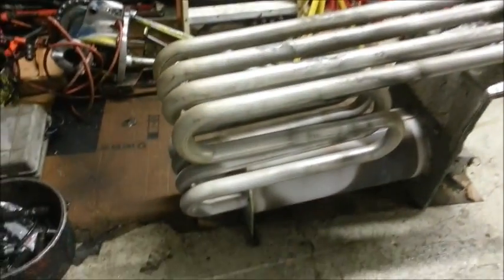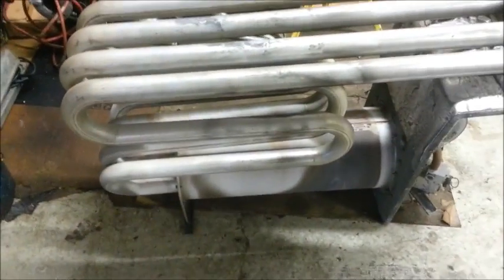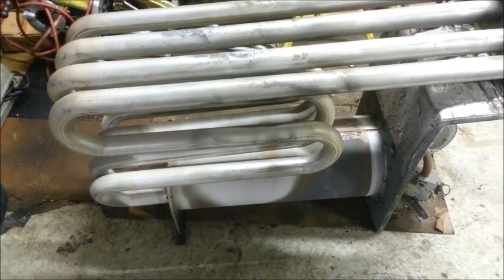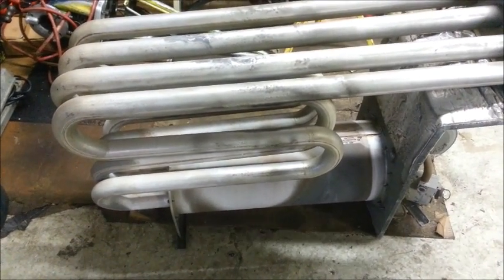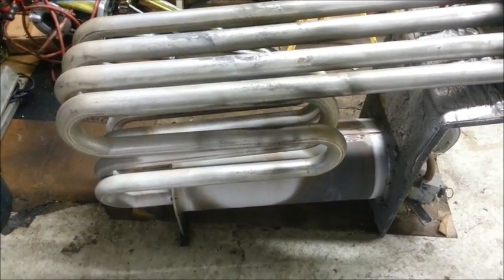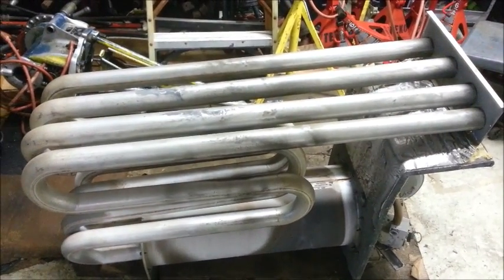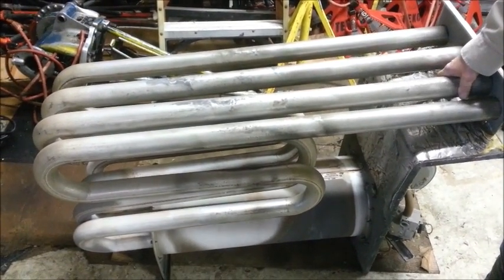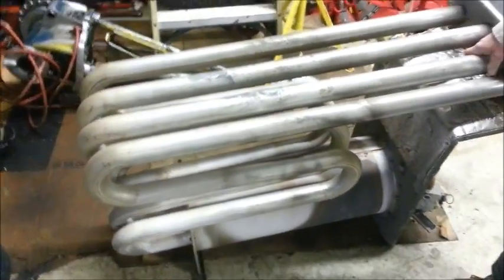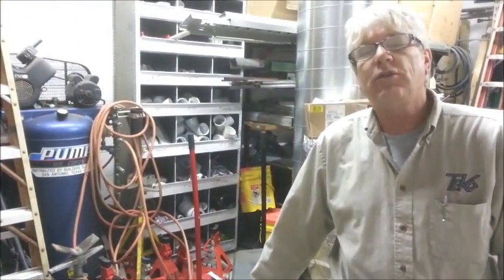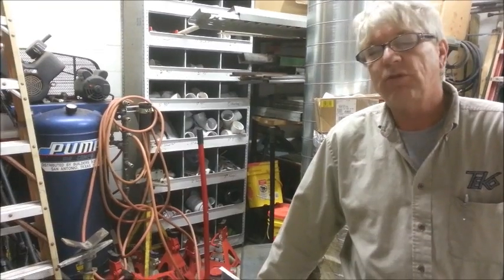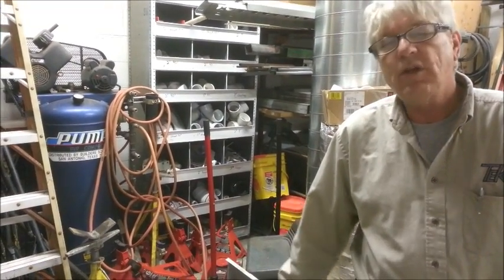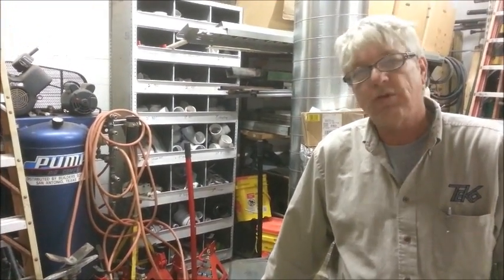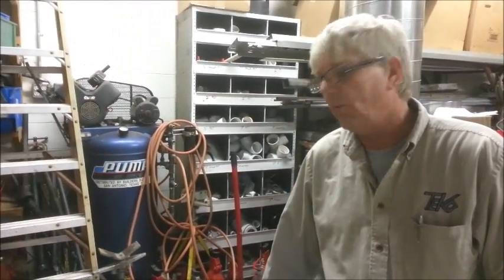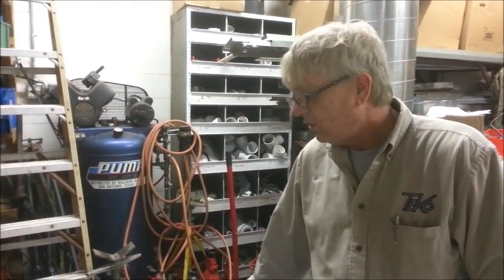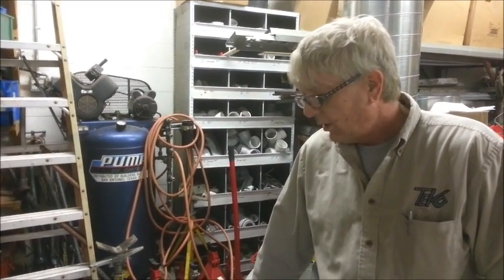You got sulfur dioxide, nitrogen oxide, carbon monoxide, carbon dioxide. So all these gases form an acidic compound. And the funny part is that a lot of this degradation takes place during the summer. This heat exchanger is exposed to low temperatures, and with high humidities on the outside, you get condensing on the inside.